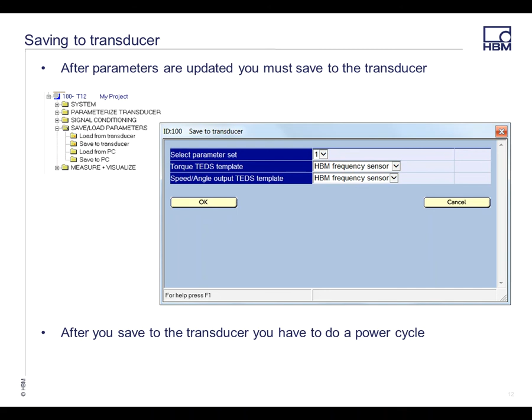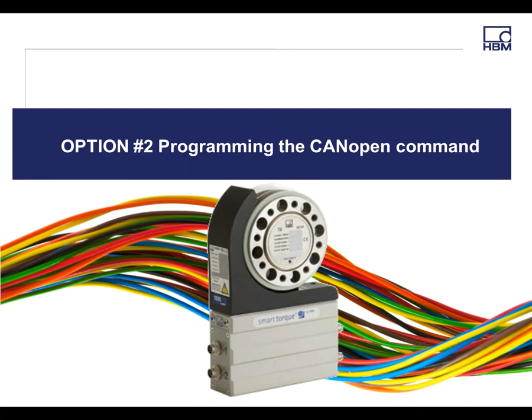There's another way to do it: set operational mode through programming via CAN. We have a manual that details all the interfaces, basically an address and a code number. The address of your torque transducer is found on the T12 Assistant when you first pull up that scan. Our default address is 110, but you can change this if you have multiple torque transducers on one rig.